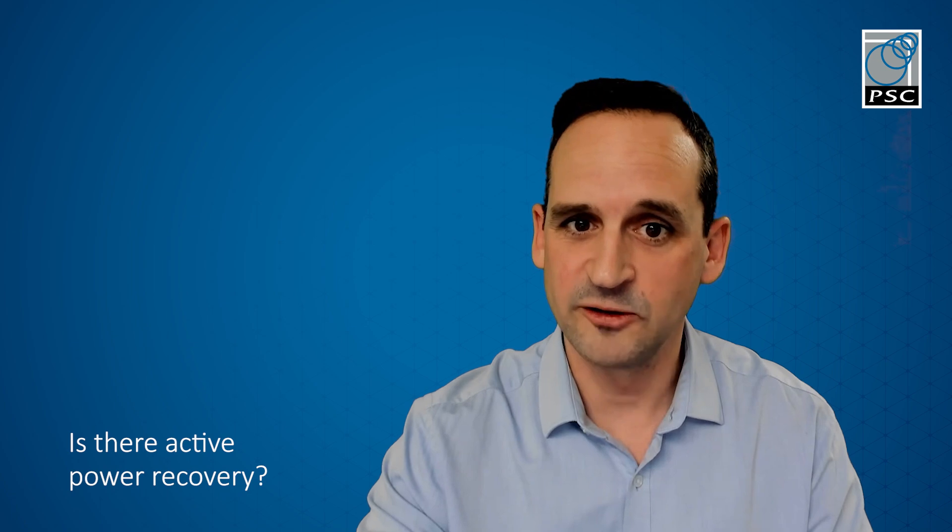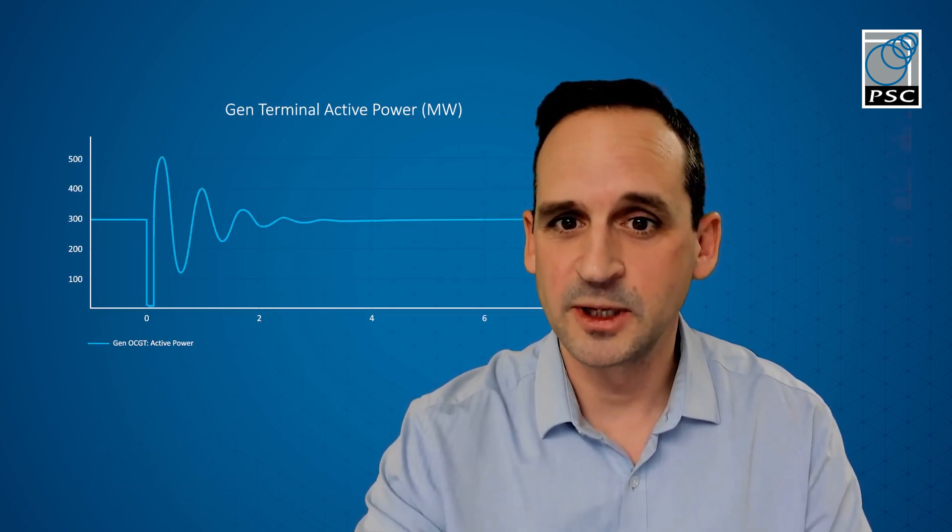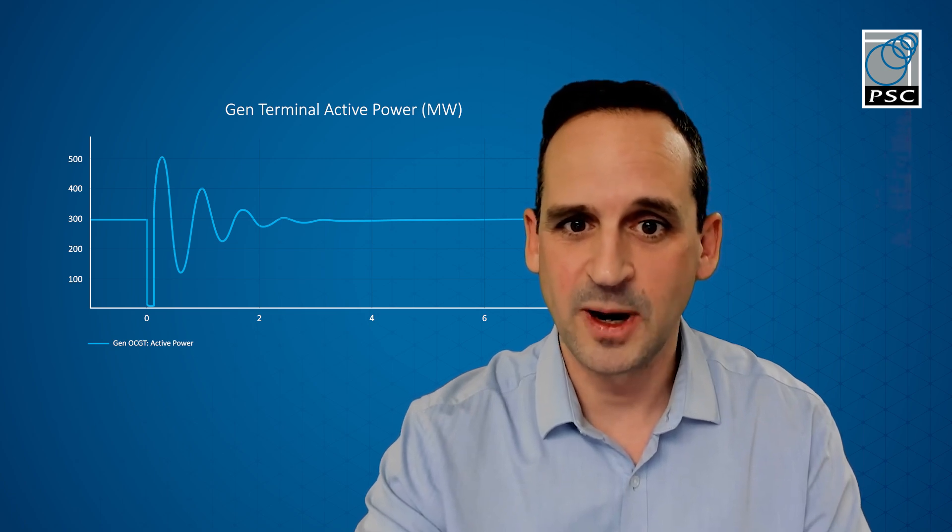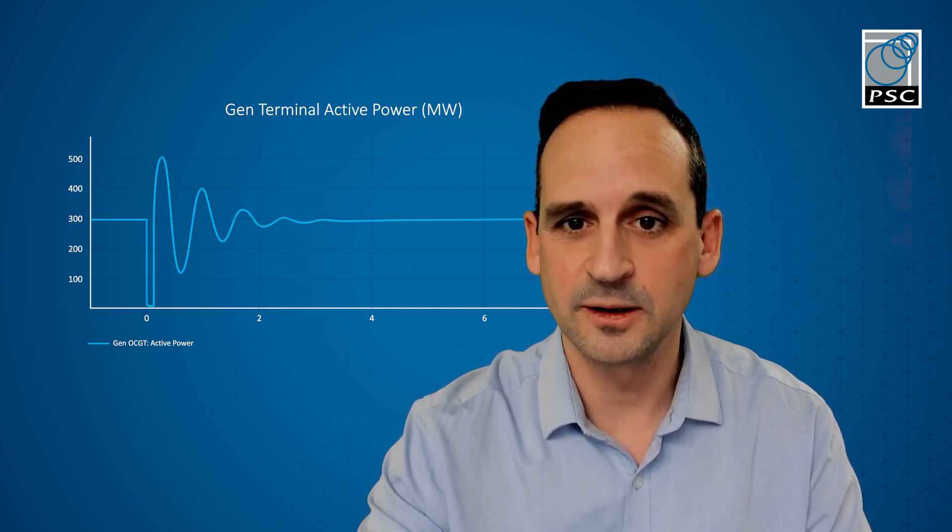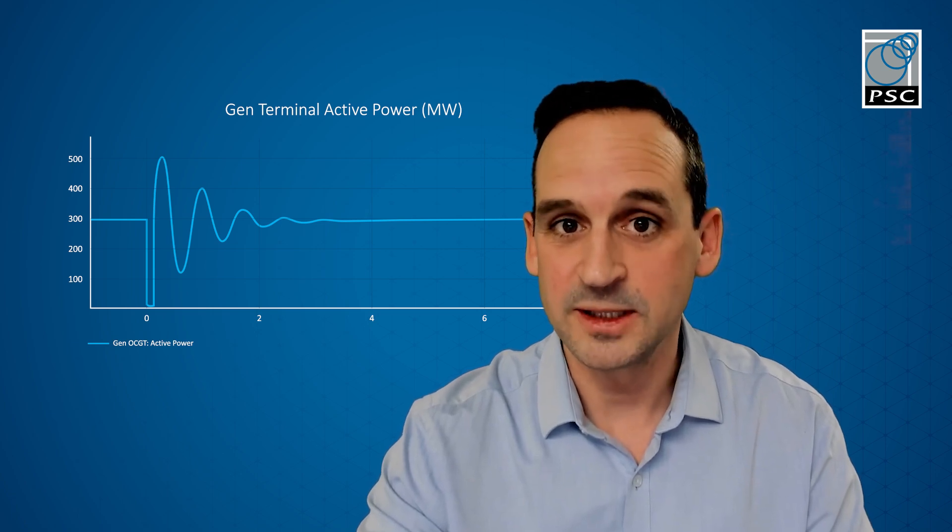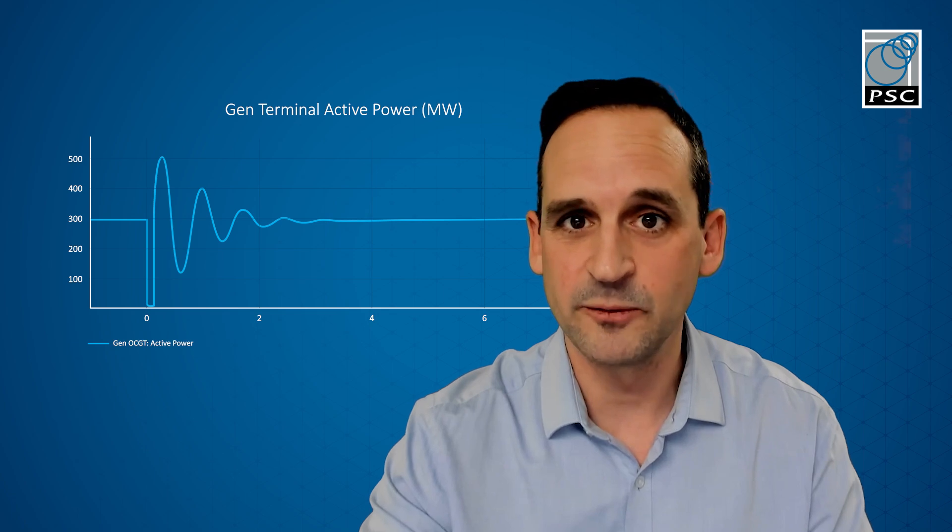Secondly, is there active power recovery? If we look at the generator power output here, it can be seen that the generator remains connected during the fault. Active power recovery occurs within half a second. There are oscillations, but these are permitted in the grid code as long as the energy delivered is equivalent to 90% of the original active power.